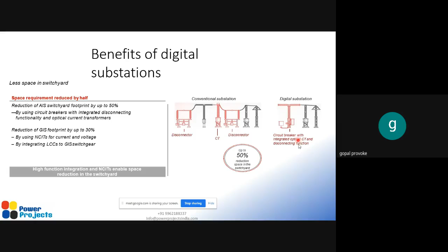In a conventional substation, we use a disconnector, CT, another disconnector, and a circuit breaker. In a digital substation, all these equipments - disconnectors, CT, and breaker - can be combined into a single module. This red equipment shown is a circuit breaker with integrated optical CT and disconnecting function, integrating all these functions. Since the optical CT occupies very little area, it can be integrated into a single equipment.